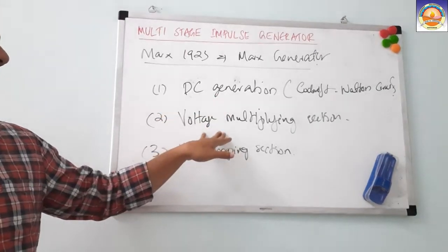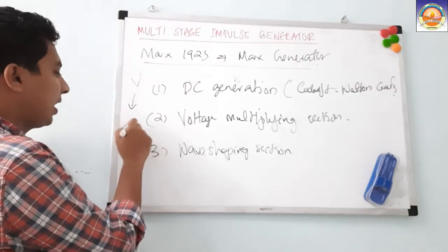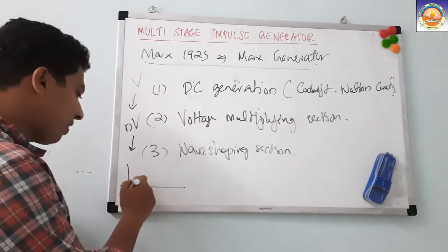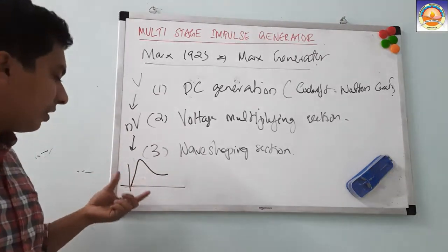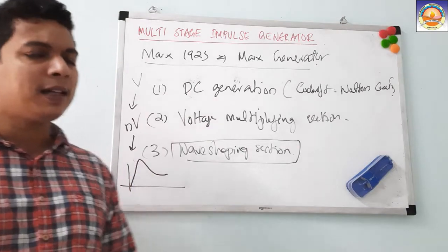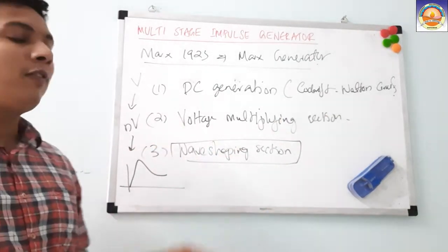The high voltage DC goes through the voltage multiplier section where it is multiplied to N times V. Then the wave shaping section ensures whether it is a 1.2/50 microsecond lightning impulse or a switching impulse waveform. In the single stage we had just two capacitors — source and load — but here we will have several source capacitances. Marx's idea is simply that.